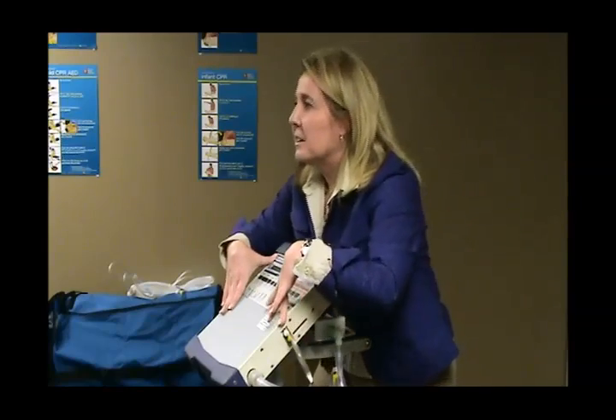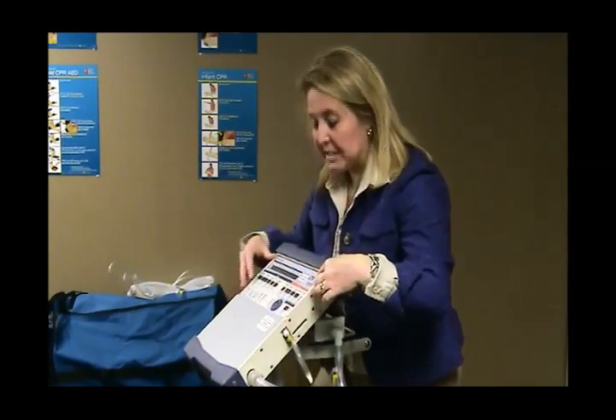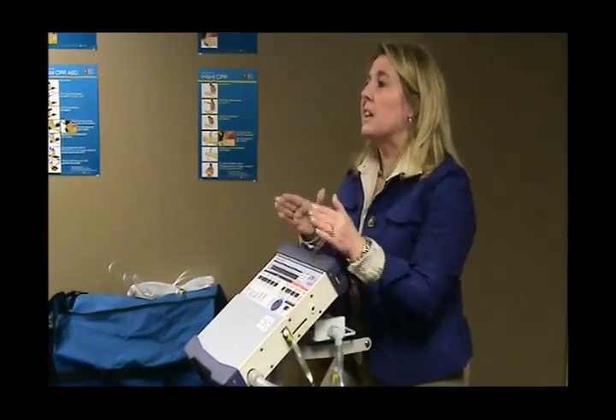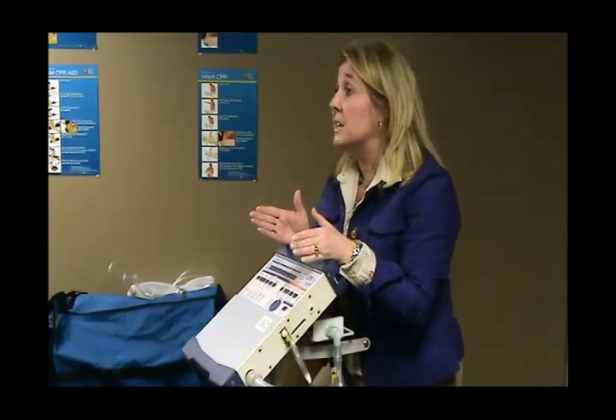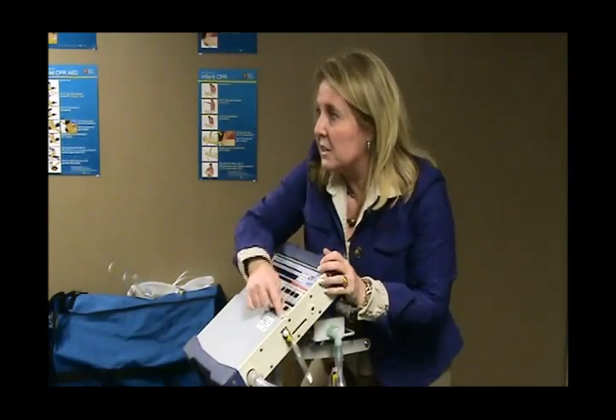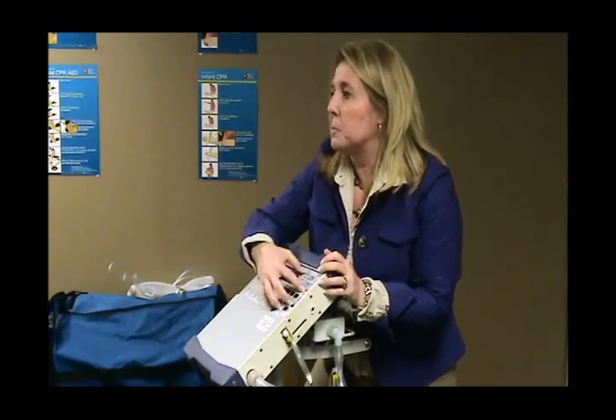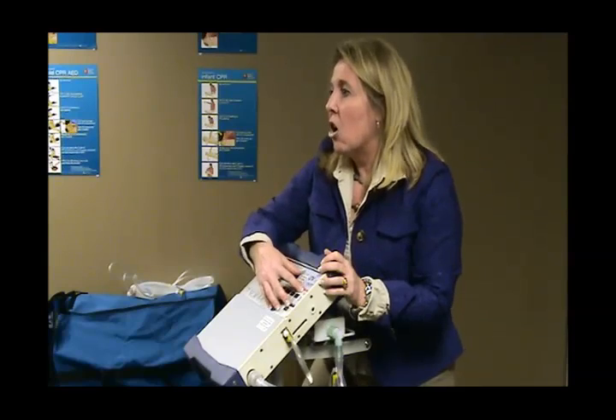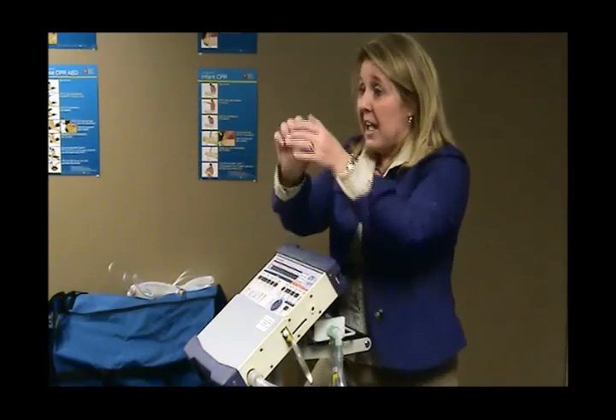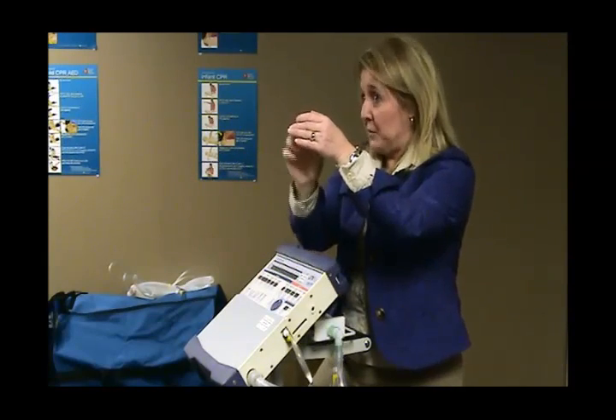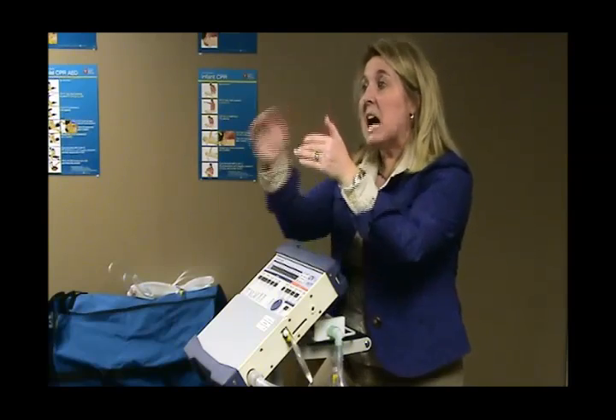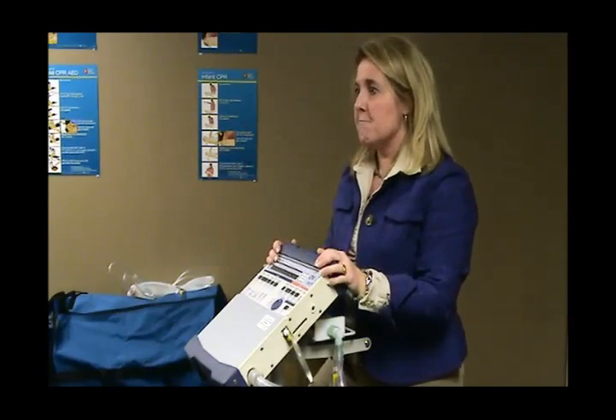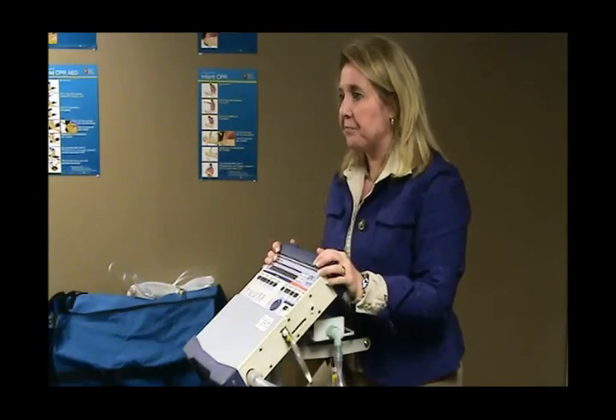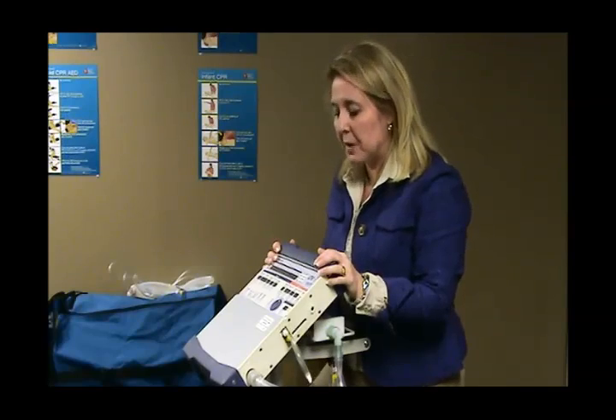Question. This one says an LTV 900, what's, Yep. is that This one is an 1150? 1150. Okay. So the 1150 and the 1100, the PEEP is inside the ventilator, and so it is PEEP compensated. On our older ventilators that have an external PEEP valve that you have to screw in, that is not PEEP compensated. Yep, that's what I'm used to, with the external PEEP valve.